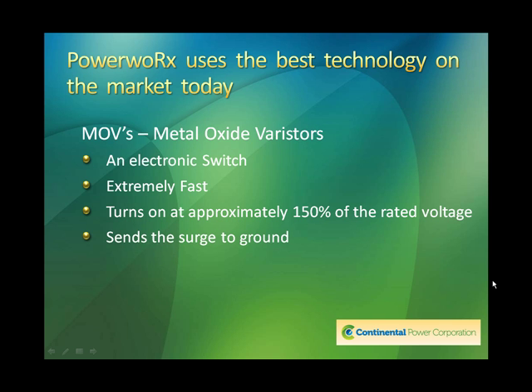It becomes the lowest impedance path. So these devices have to be able to source huge amounts of current. If we look at our commercial PowerWorx units, they're rated up to 120,000 amps over an extremely short period of time, though. Keep that in mind. The turn on is at approximately 150% of the rated voltage, and it sends all that energy to ground. And then once the voltage drops below that threshold, the switch turns back off.